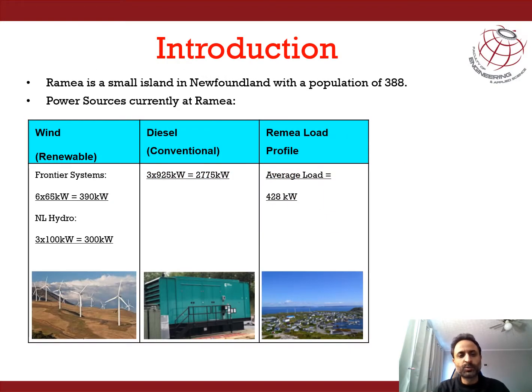Ramea is a very small island in Newfoundland and has a population of slightly less than 400, that is around 388. The primary source of power in Ramea is diesel generator sets. There is a total installed capacity of 2775 kilowatt of diesel generator sets.